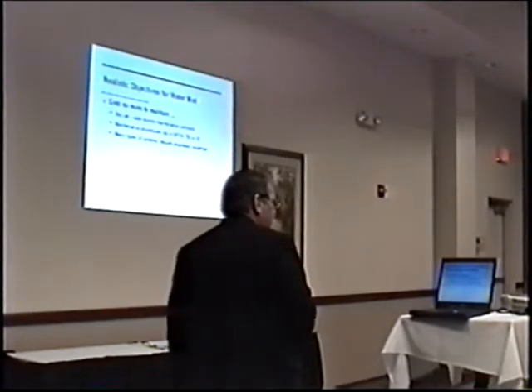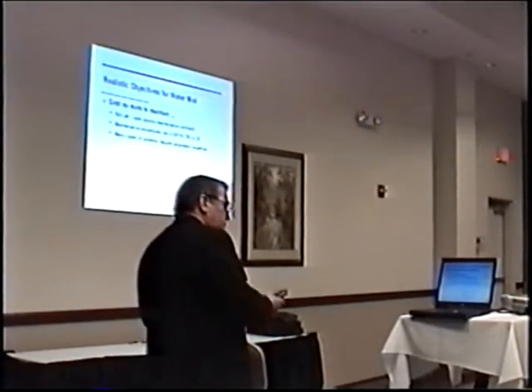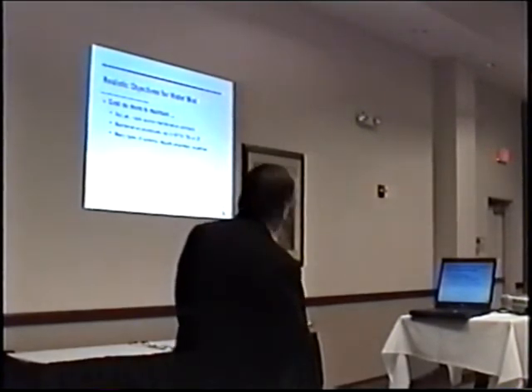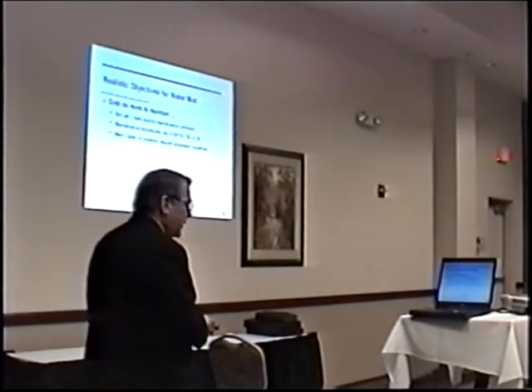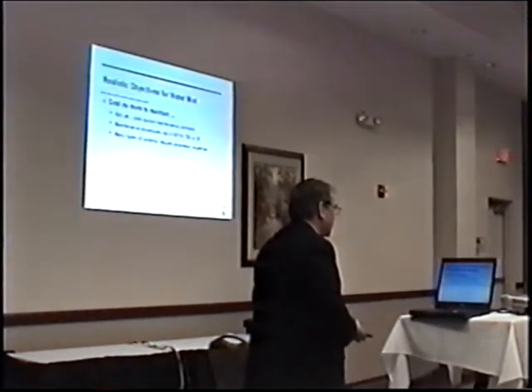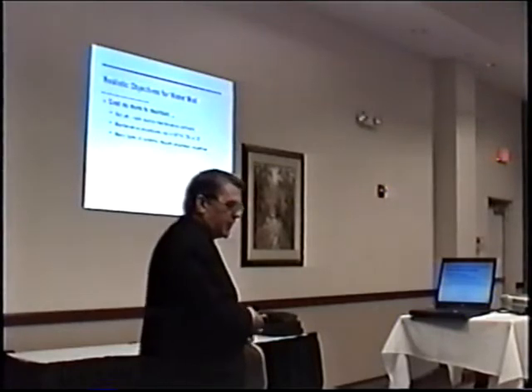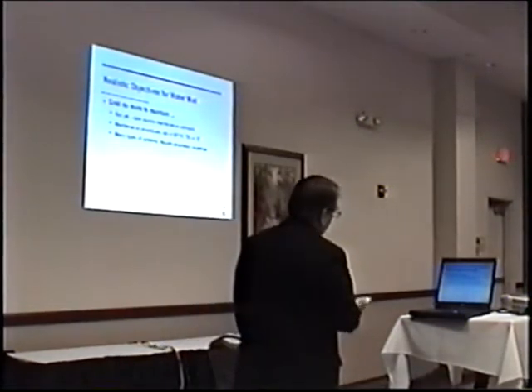What about maintenance? Well, right now, instead of going to 3 different possible competing companies in your local town to maintain your water mist system, you're probably going to fly somebody over from Finland or Germany or maybe in from Baltimore to maintain your system. So it's difficult to get sole source. It's difficult to get competitive maintenance costs on the systems. The maintenance procedures for water mist systems are still being pioneered. I'll talk a little bit more about that. There's a lot of proprietary expertise. The Marioff company out of Finland is not going to teach just anybody who doesn't have a signed agreement with them how to maintain their systems. So that's not going to win the day.